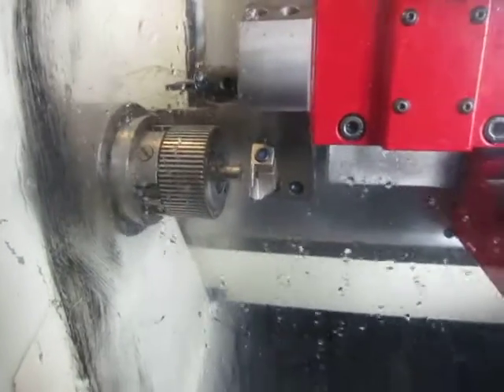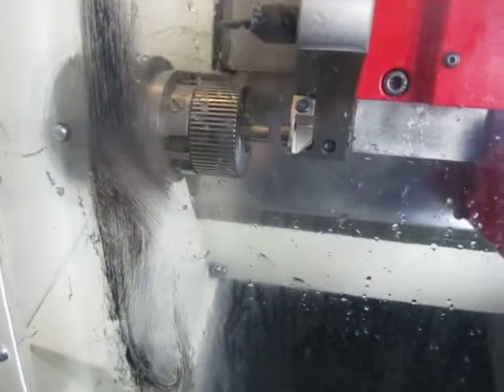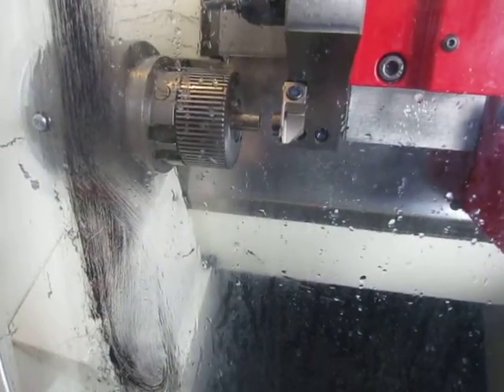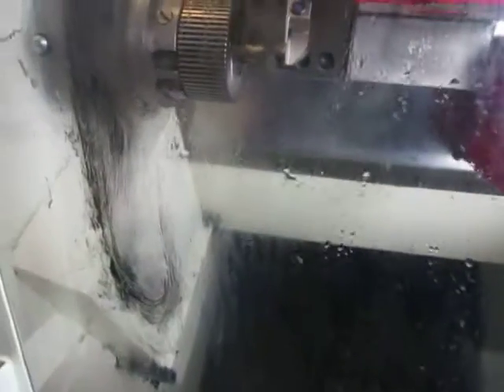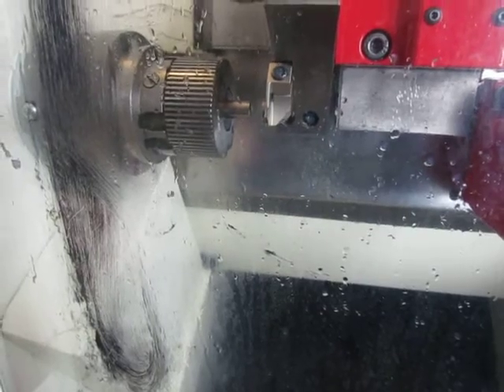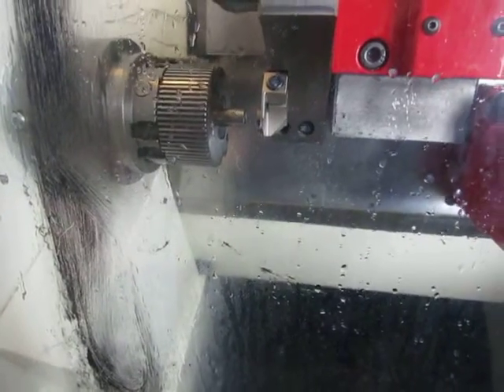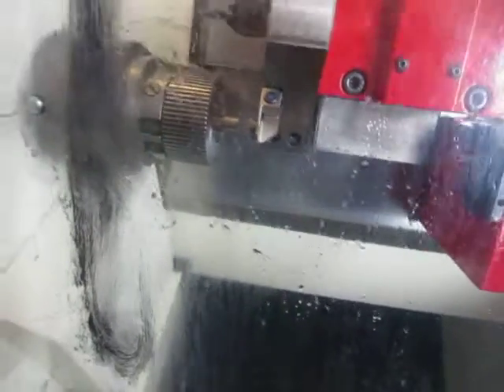The thing is that the motor accelerates from 0 to 3000 RPM relatively normally, but when I want to machine something at 4000 RPM, the thing that I didn't like is I needed to wait too long for the spindle to get to 4000 RPM, and it was something strange. So this is why I went to try to change parameters.